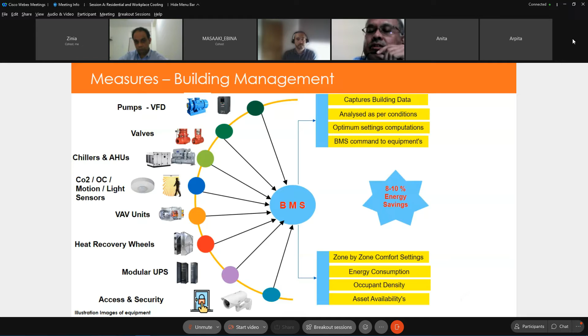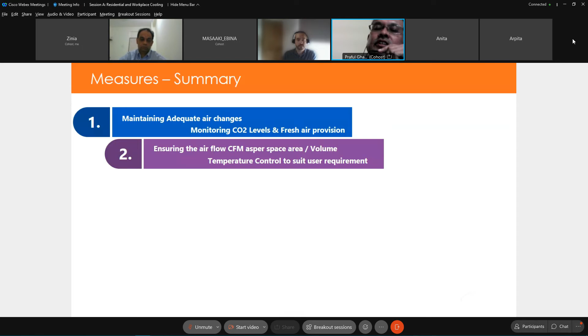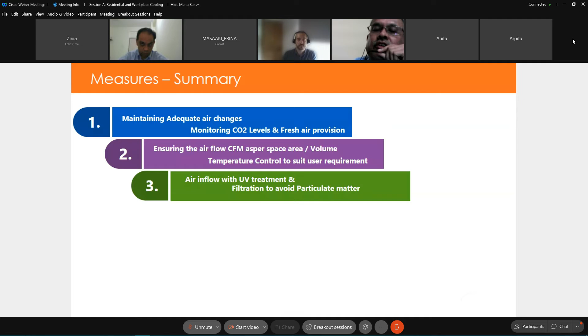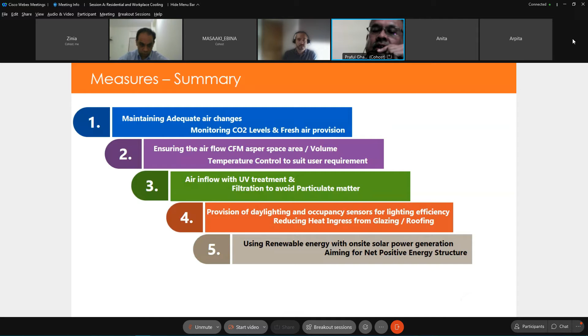Now, a quick summary of the measures. When these buildings are functional, air changes are maintained, CO2 levels are monitored electronically, and fresh air provision is done whenever thresholds are reached. CFMs are ensured in all pockets of the various building spaces, temperature is set to suit user requirements, the air inflow has UV treatment as well as filtration to avoid particulate matter, and there is provision of daylight and occupancy sensors to reduce lighting load based on conditions around the building.